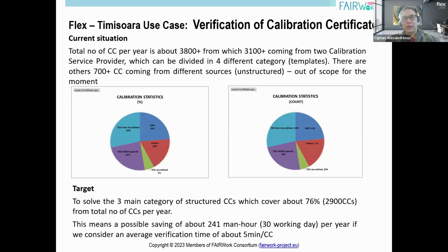The current situation is that we receive an average of more than 3,800 calibration certificates per year from providers of calibration certificates, of which 3,100 come from 2 calibration service providers and can be divided into 4 different category templates, which are much more structured. There are also more than 700 coming from different sources, which are not structured and do not respect a specific template, which is out of scope for the moment for this project.